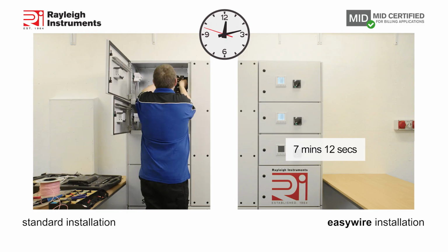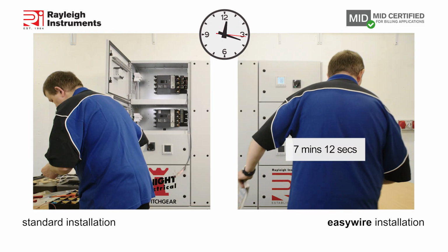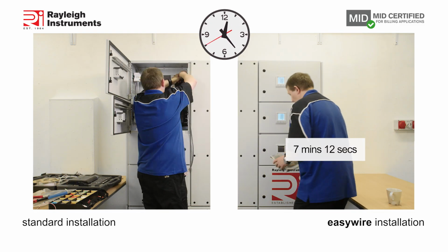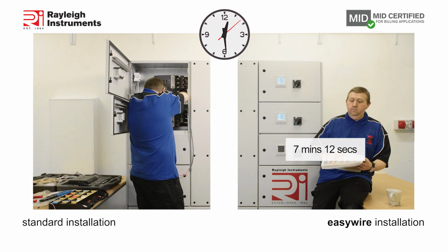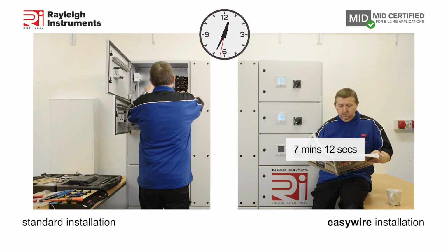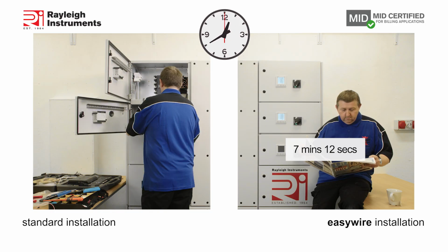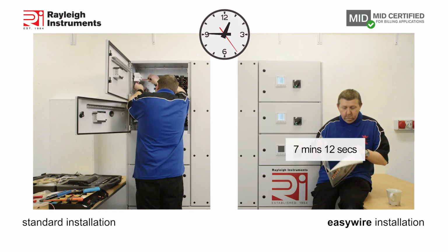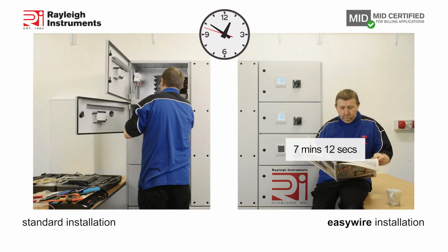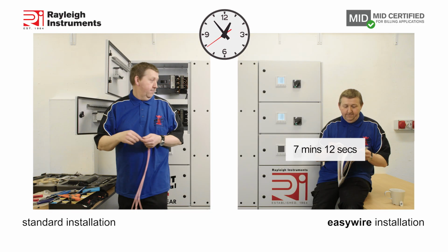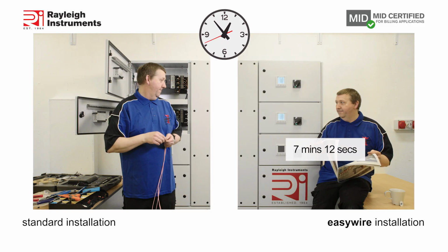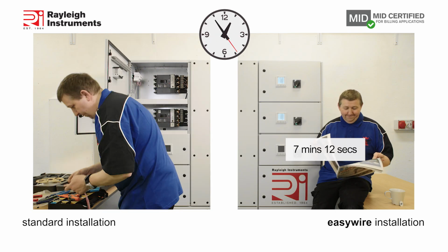Meanwhile, back at the standard installation of the same setup, there is still quite a way to go. Each 3-phase current transformer needs 6 cables cut, labeled, and ferrules added. These also need to be screwed into the terminals, as there is no plug-in option here. This means that your engineer is on site for much longer installing the meters and CTs, and there is also more chance of an error occurring in the wiring.